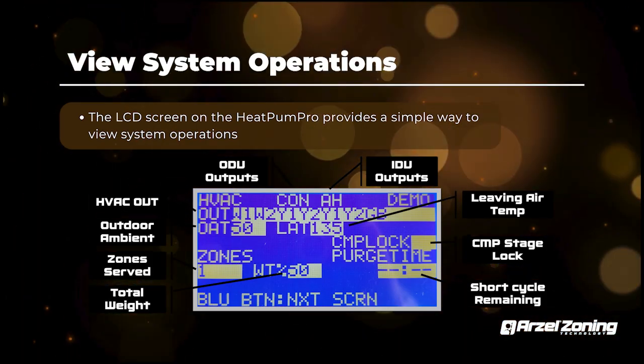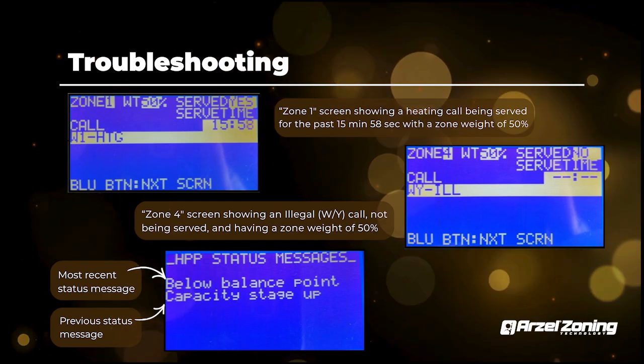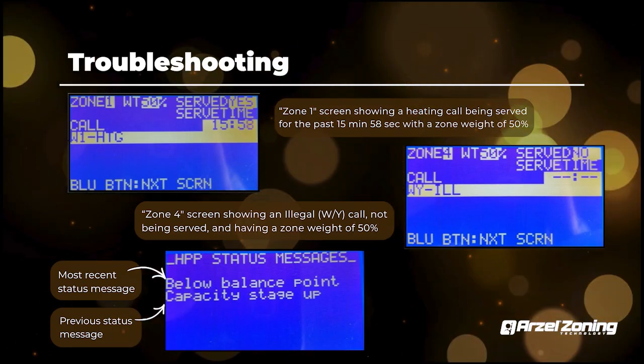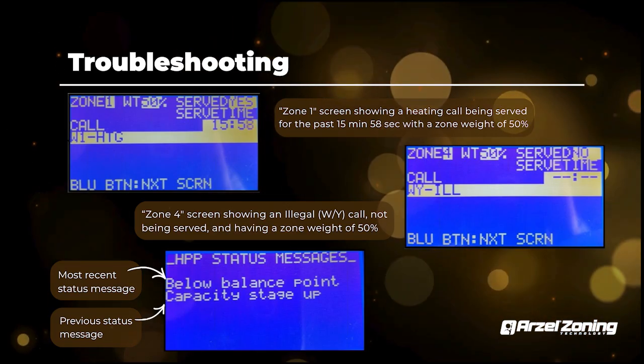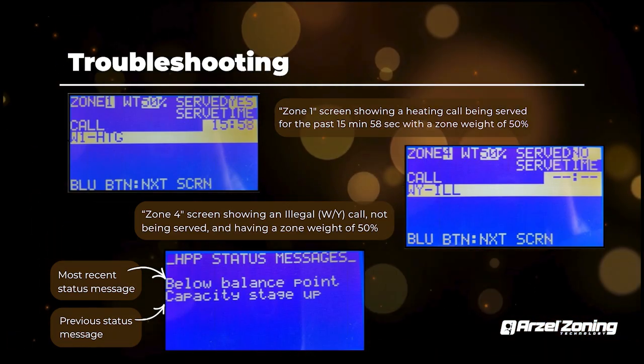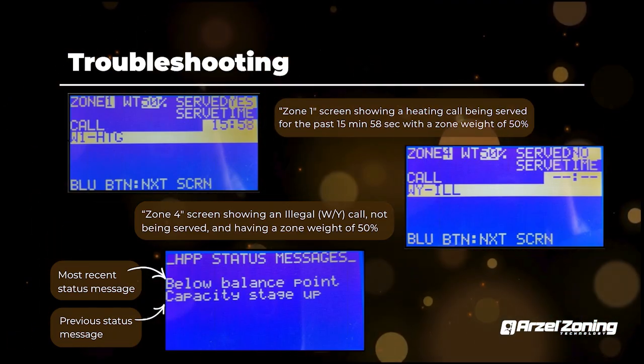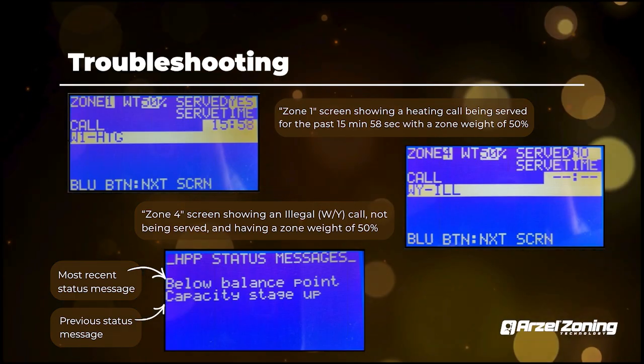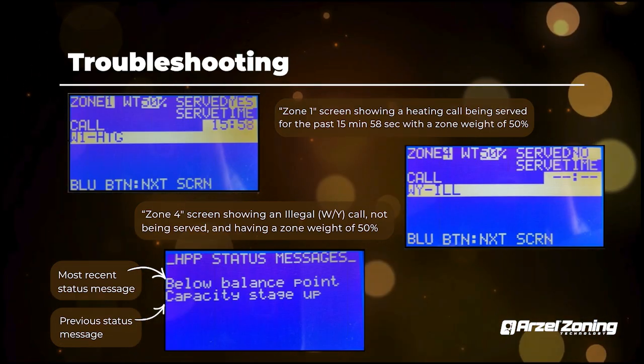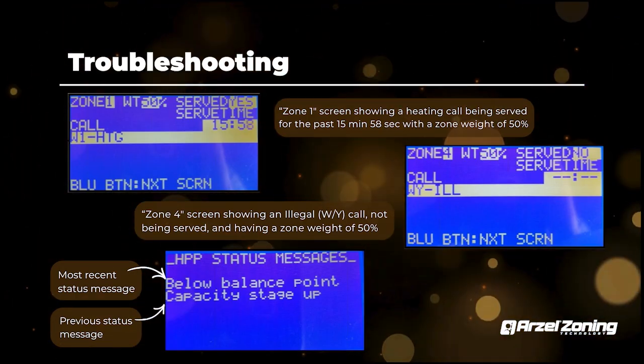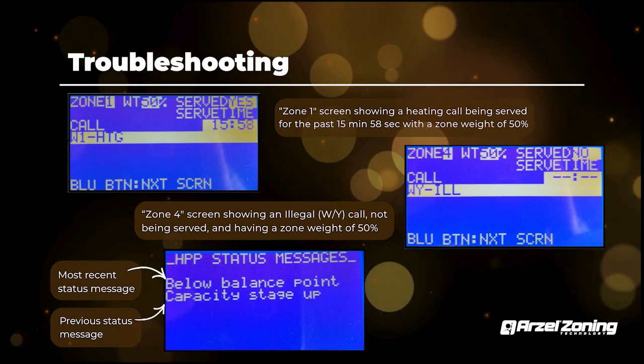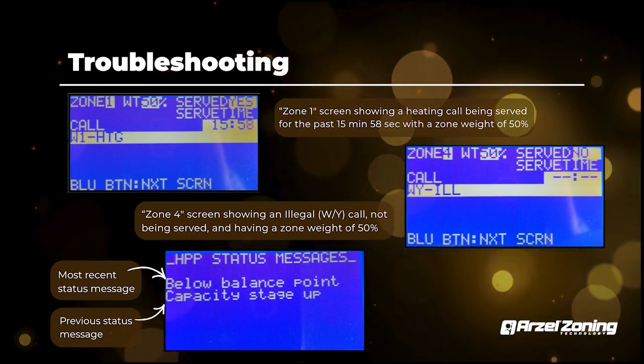But from that main screen, if you hit the enter button, it's going to go to each one of your thermostat calls. So in the top there, you got zone 1. It's got your weight percent, so the amount of ductwork on that zone. Tells you if it's served or not, so it'll say yes or no. It'll give you a serve time, so how long have we been running this call? And it'll have a timer there. It goes up to 99 minutes. So if you ever hit 99, you probably got an issue. But that's where the timer actually will stop.